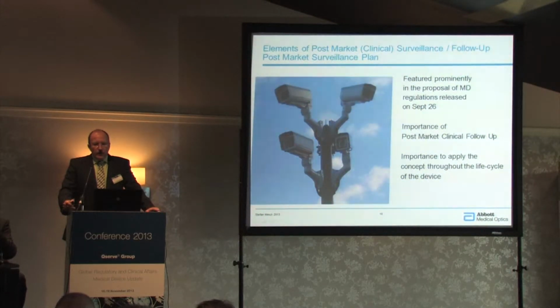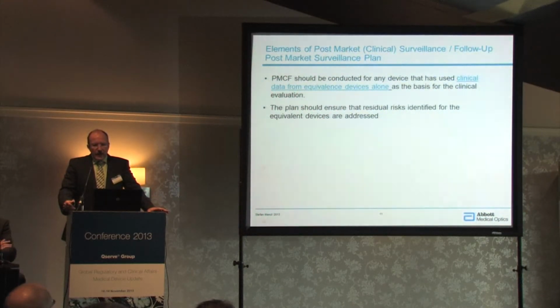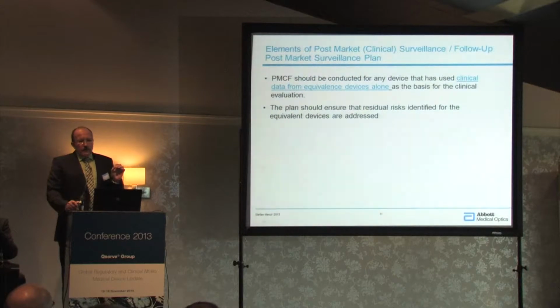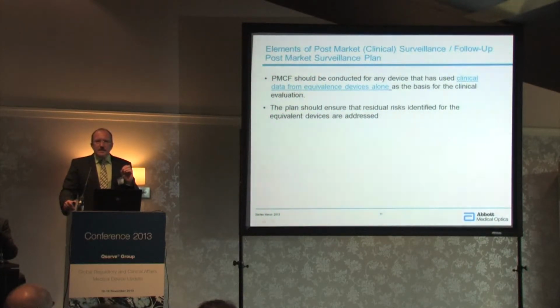What are the elements of a post-market clinical surveillance or follow-up? I think the new regulations clearly focus on clinicals, on clinical assessment, but also on clinical follow-up. And I already said there is a focus on an ongoing approach to do that exercise. It says the post-market clinical follow-up should be conducted for every device and has basically to consider data from equivalent devices, but also, in case this is not sufficient, from your own device. But it's important to not look only at your device in the post-market phase, for the reasons I mentioned earlier.